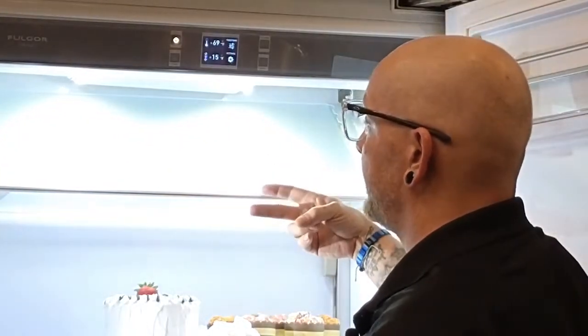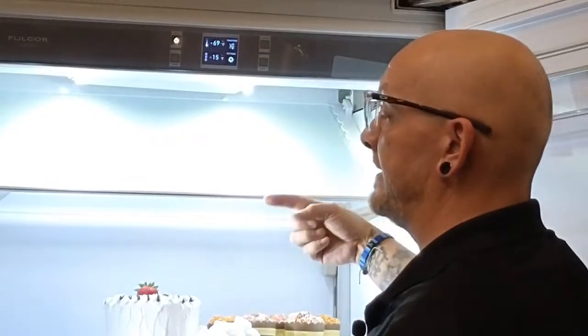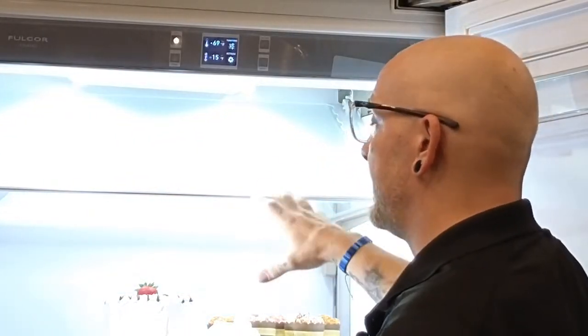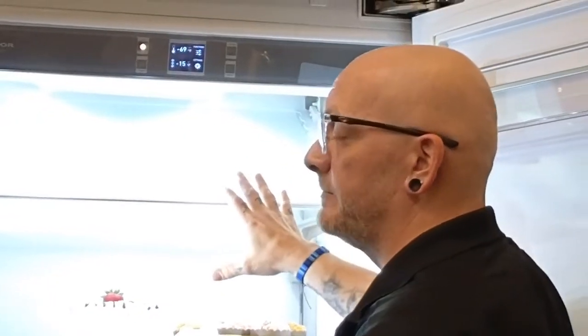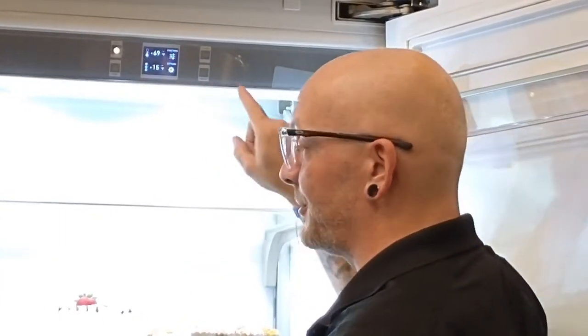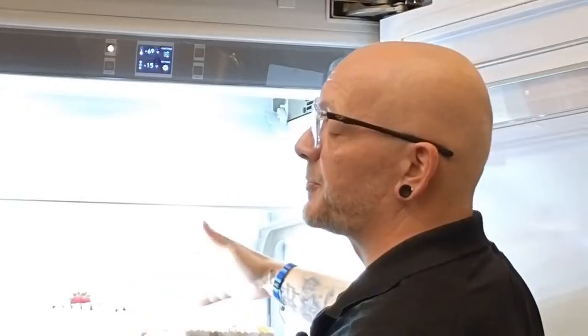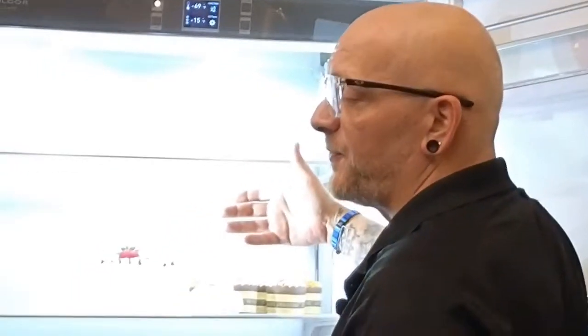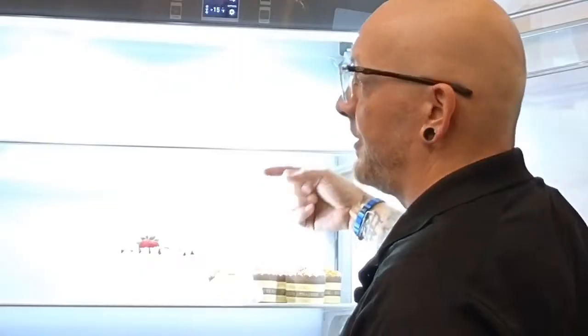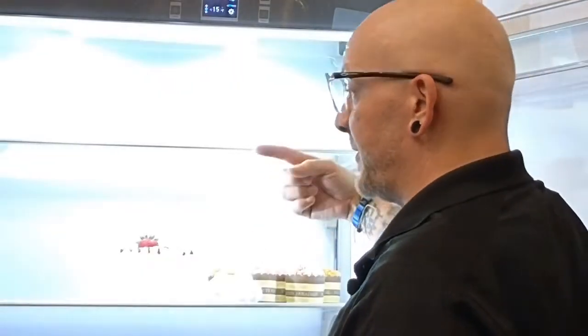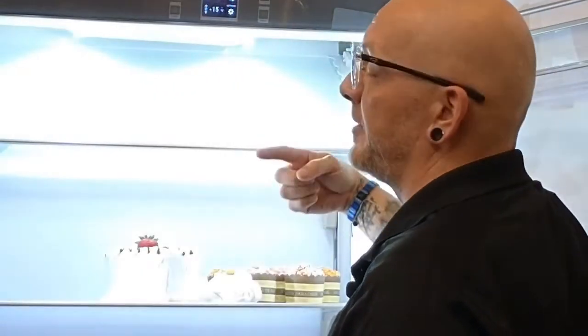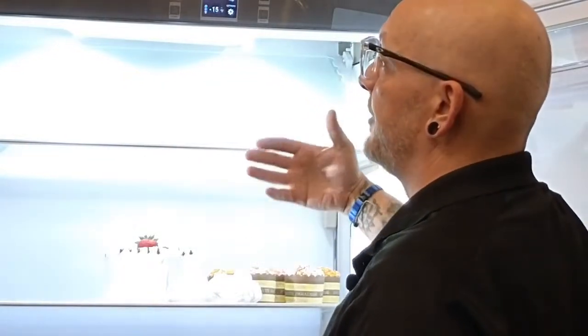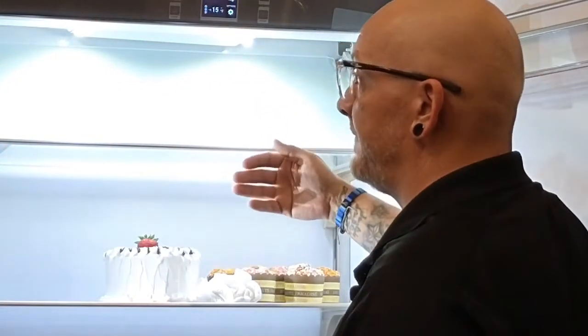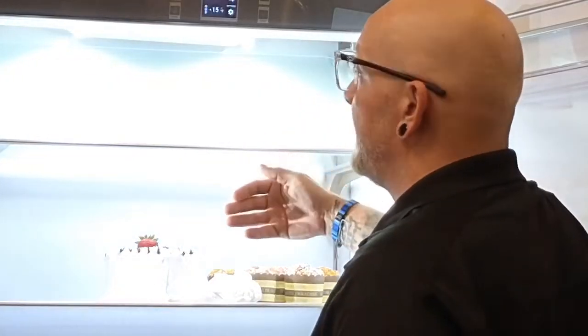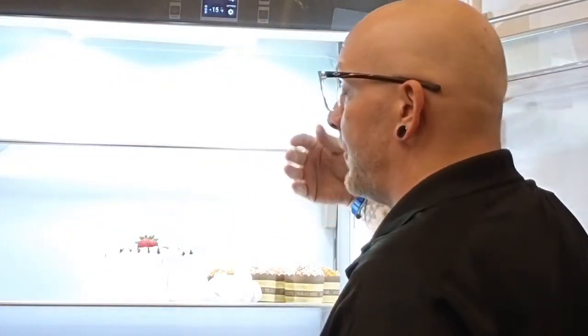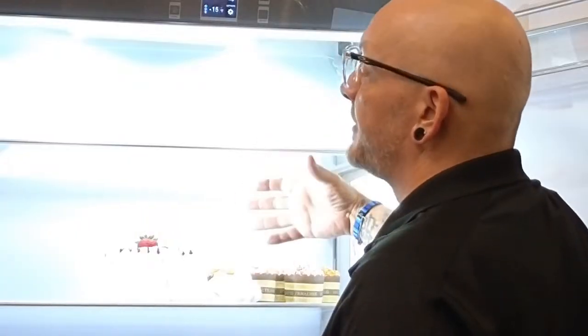functions, the settings, the manual clean. You want to pressurize the system after you do a fresh install, because let's pretend you install this machine. You did not run a manual clean. You turn the ice maker on. You leave the customer's property. Within 24 hours, 48 hours, the customer's not going to notice any ice and they're going to call for service. And it's because the ice maker is trying to fill with water, but it cannot because it's not pressurized yet. So if that step is forgotten during installation, it very well may cause an unnecessary service interaction. So be mindful, always run a water circuit cleaning whenever you install one of these machines.